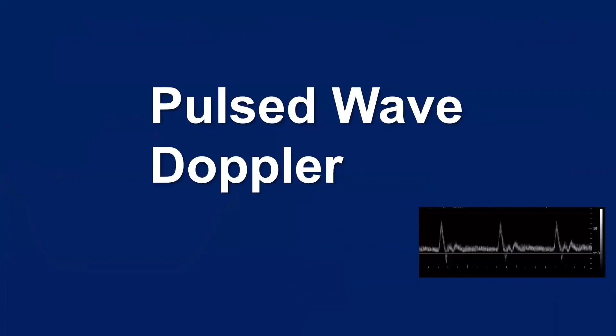So let's look first at pulsed wave Doppler. So again, the spousal hearing examination, or I guess more politically correct would be selective hearing. It only listens for blood flow information in a very specific area. The box is known as the sample volume, and that sample volume size and location is operator controlled. It's kind of a silly example, but it works. I just imagine whoever's inside my system has its ears plugged until it gets to a certain time, then it opens, it listens, and then it closes its ears again. And that way I only get information from where I want it.